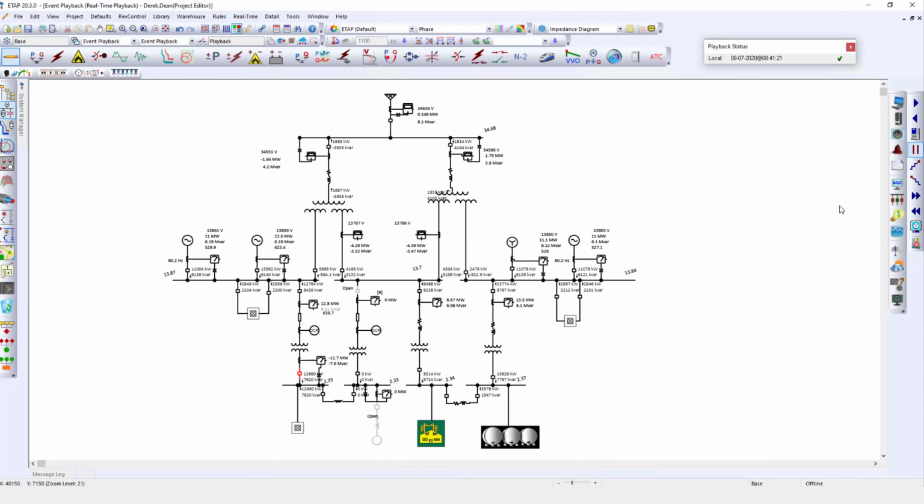See how the trainer can see the initial state where the motor is offline, and as we step forward in time, a large portion of the network becomes de-energized. This indicates to the trainer that the trainee performed an incorrect action. As we continue to step forward in time, we can see that the trainee learned from the previous steps and now is able to successfully start the motor. This is, of course, after closing the other circuit breaker, which allowed the power to be shared.